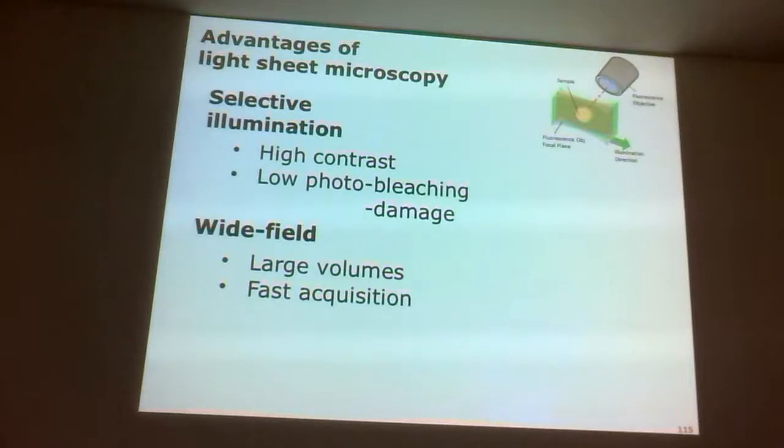Okay, what is big for you? I can ask that question. What is big? Okay, so I would guess light sheet can typically get hundreds of microns by hundreds of microns by hundreds of microns at 1 to 2 micron resolution, easily. That would be quite a good way to do it. But of course, the question you're asking depends on the numerical aperture of the optics that you choose to use. So it's not huge, but it can do quite nice large volumes very, very quickly.